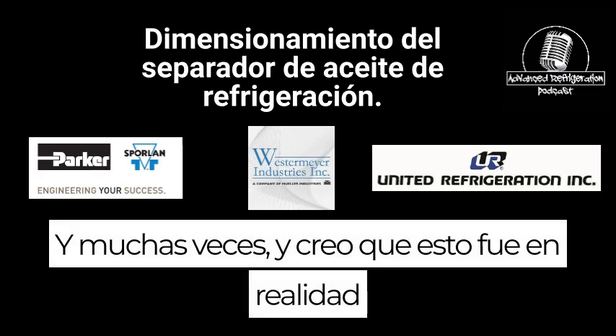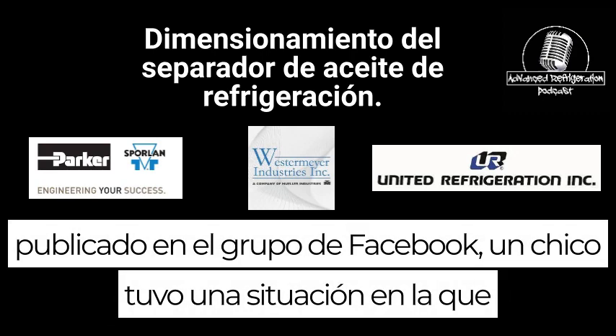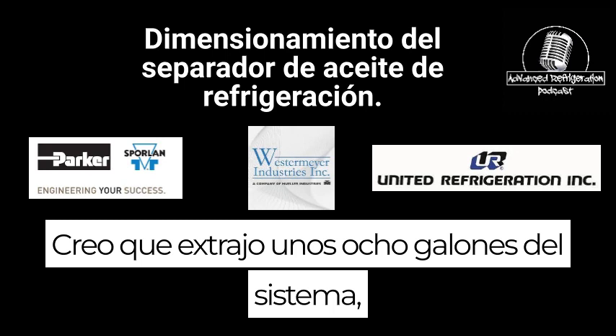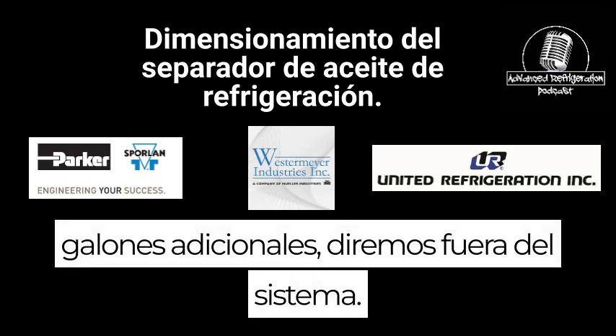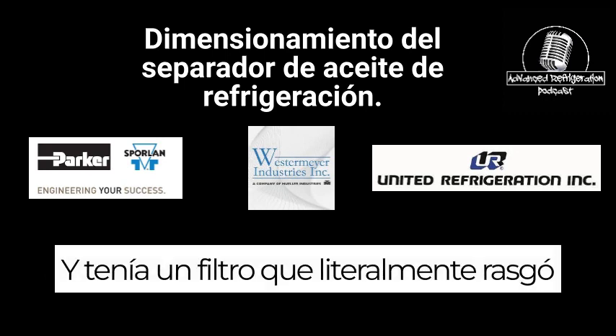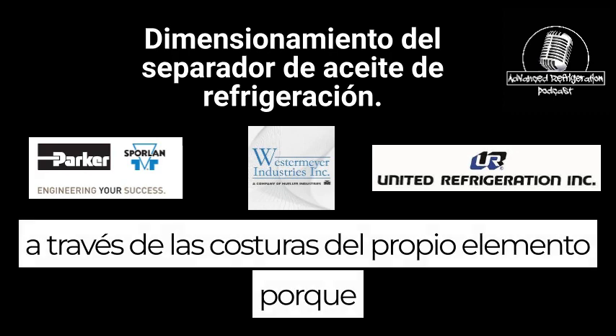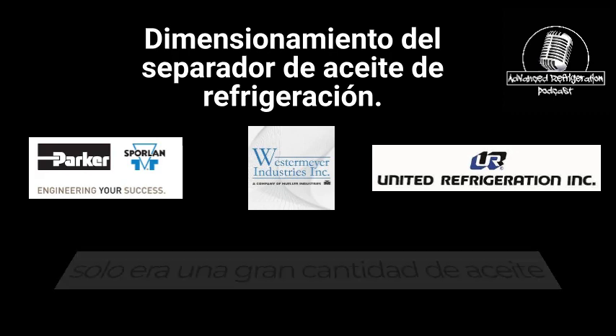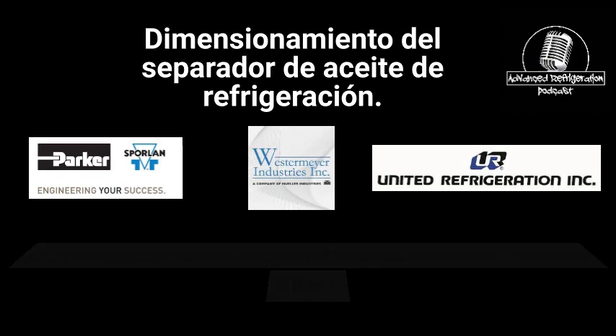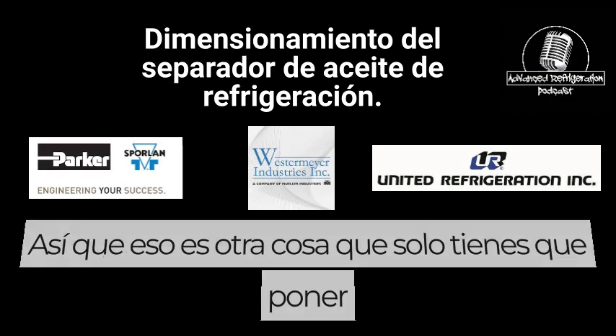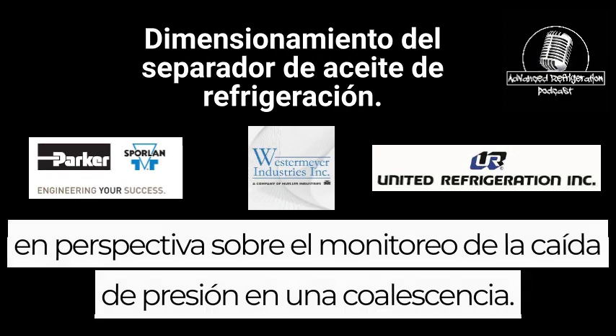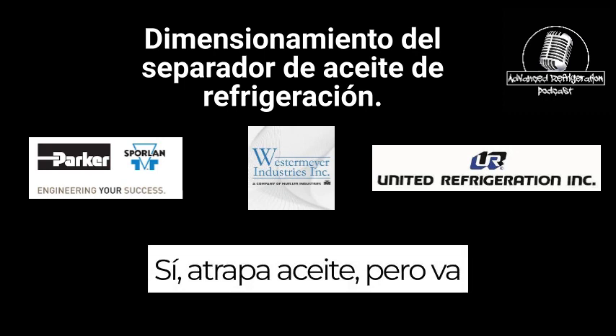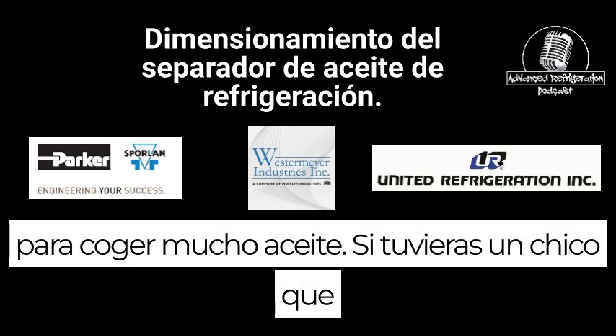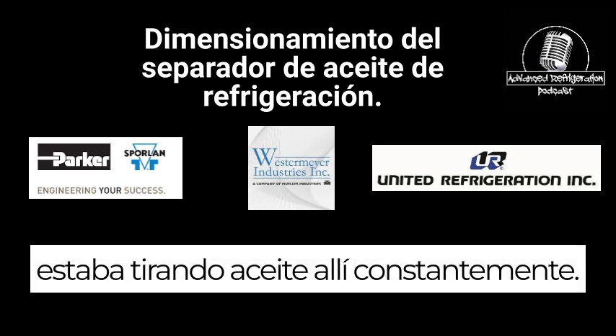And a lot of times, and I think this was actually posted on the Facebook group, a guy had a situation where I think he pulled maybe 8 additional gallons out of the system, and he had a filter that literally ripped through the seams of the element itself because of the massive amount of oil getting pumped in through that filter. So that's something else to put in perspective about pressure drop monitoring on a coalescing filter. Yeah, it catches oil, but it's going to catch a lot of oil if you had a guy that was dumping oil in there constantly.